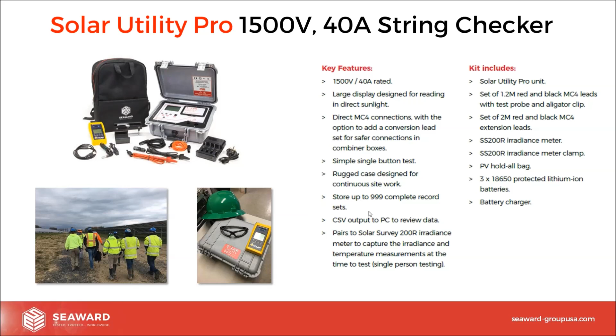There's no point taking a 1kV voltmeter there, that's not going to do it, and we can't be shorting out those panels quite easily. So what we devised was a Solar Utility Pro kit. This is going to hit the headroom of the 1500 volt, 40 amp that you need to work on a utility scale PV plant. We also looked at the design, so often tools are not designed for such rugged environments. Ours is housed in a Pelican case, and again you're going to get the irradiance and temperature detail.